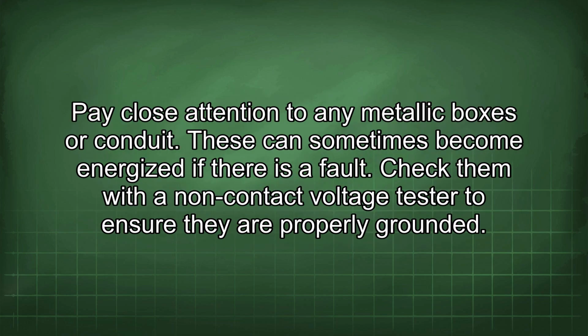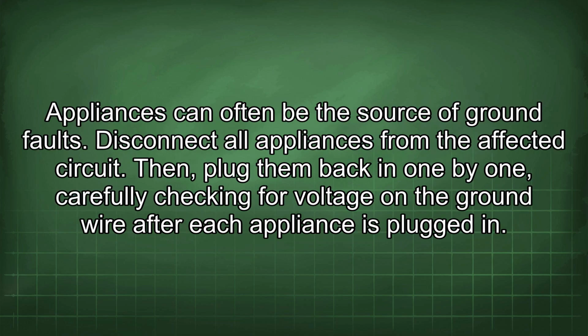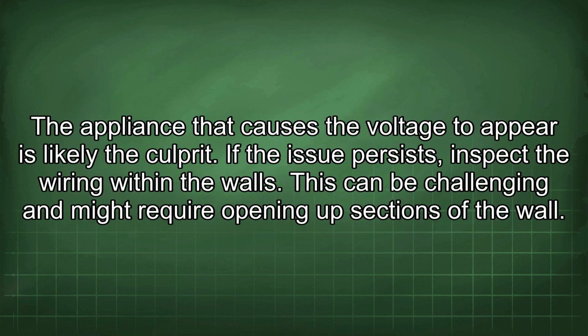Pay close attention to any metallic boxes or conduit. These can sometimes become energized if there is a fault. Check them with a non-contact voltage tester to ensure they are properly grounded. Appliances can often be the source of ground faults. Disconnect all appliances from the affected circuit. Then plug them back in one by one, carefully checking for voltage on the ground wire after each appliance is plugged in. The appliance that causes the voltage to appear is likely the culprit.